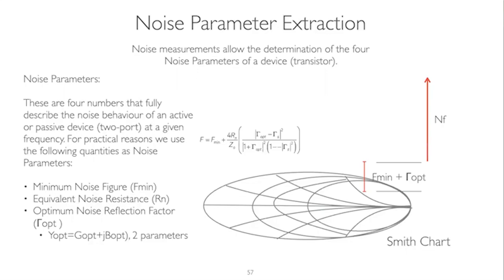Theory says that to extract noise parameters, I need 4 points, and based on those points, we can fit them and extract the noise parameters. In reality, we measure way more than that because some points are not necessarily good - it's very noisy data, so you'll get jittery data.